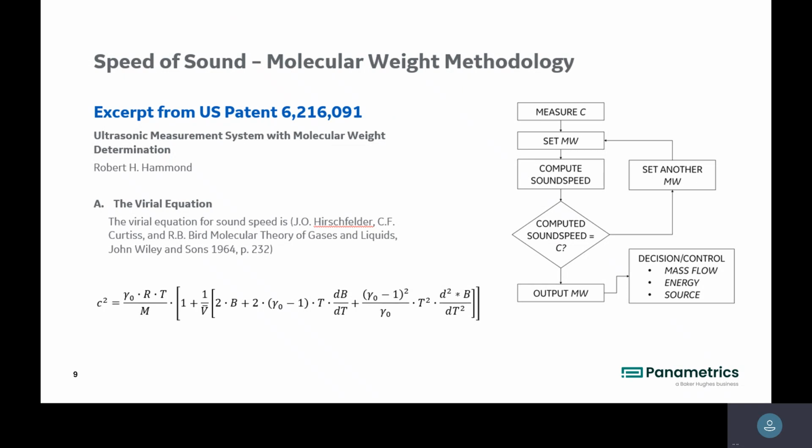Basically, it's just the relationship between the gas sound speed versus the molecular weight, and of course the temperature, and there's also a pressure term in there. But anyway, you can calculate the molecular weight based on the sound speed measurement using this so-called virial equation.